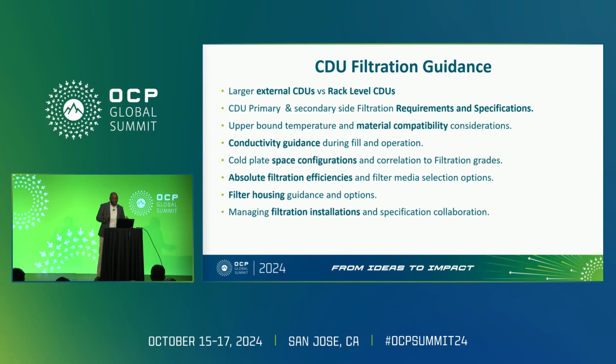So, different filtration setups for CDUs. There are different permutations that could favor full flow filtration or side stream filtration. Full flow filtration might be appropriate when you have a low flow scenario and you can harness the advantage of having that full flow filter, where you can clean up quite rapidly and you have that precise filtration.